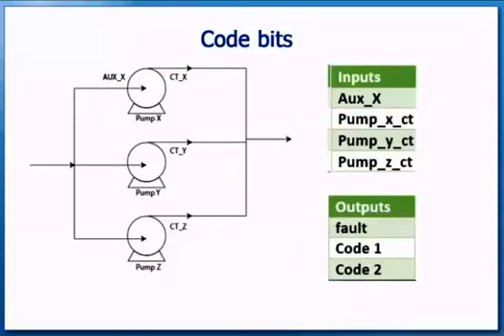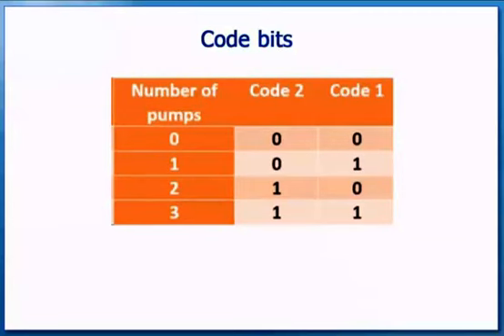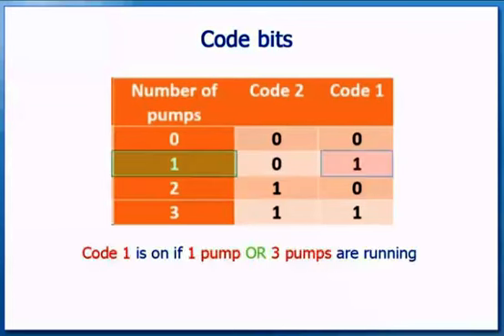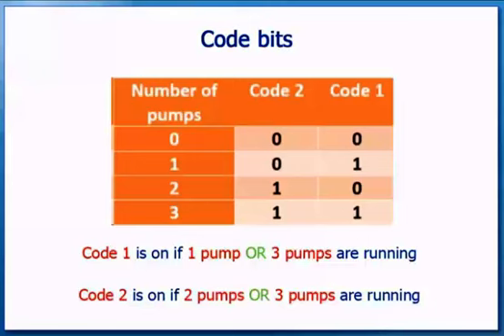The next step is to look at the code bits. We need to program the two code bits so that they indicate how many pumps are running. This table shows how we can use two bits to show how many pumps are running. Code 1 comes on when one pump or three pumps are running. Code 2 comes on when two pumps or three pumps are running. Note that we are not specifying which pumps, just the number. We can create three internal relays: one pump, two pumps, and three pumps.